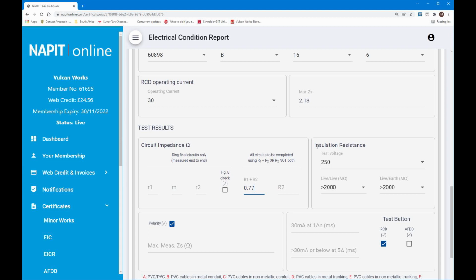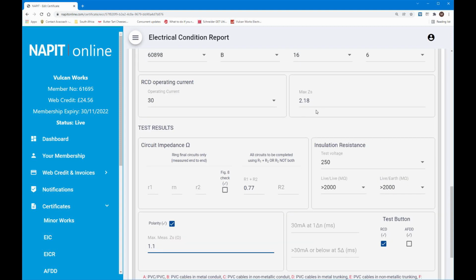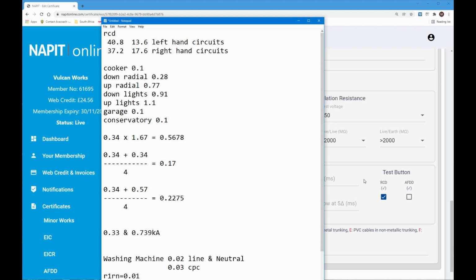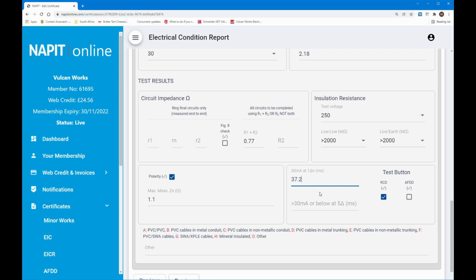Now you'll notice on this one I did an insulation resistance test at 250 volts. The reason for that is in the upstairs socket circuit there were USB charging points which I could not isolate. So to be safe I could only do it at 250, so that's why I've set it at 250 here. No problem with the readings, so I was quite happy with that. I couldn't do it at 500 because I could have risked damaging the components. So the maximum measured ZS here would have been 0.77 plus the 0.33, I believe that's 1.1, my math is correct, and that's well within that 2.18 for this particular type of circuit. Again, the RCD readings are identical, so 37.2 and 17.6. So that's that one done.